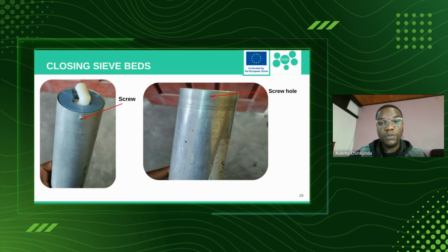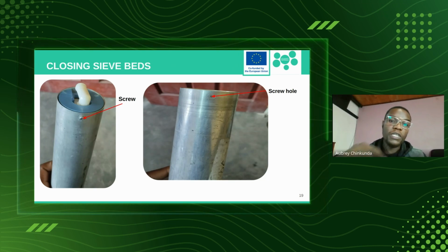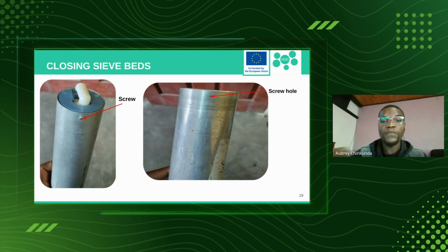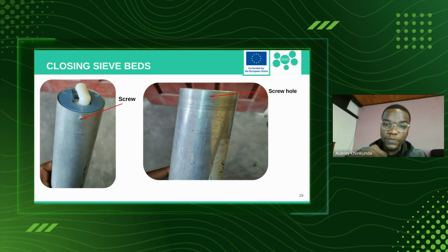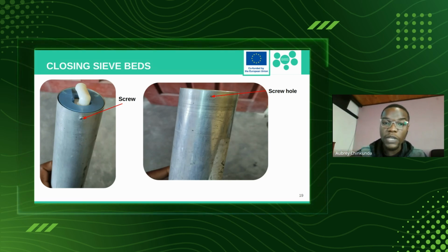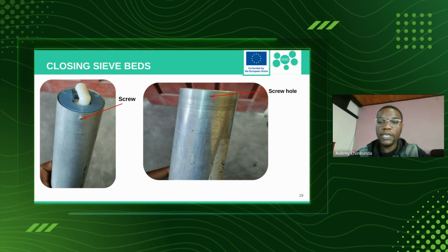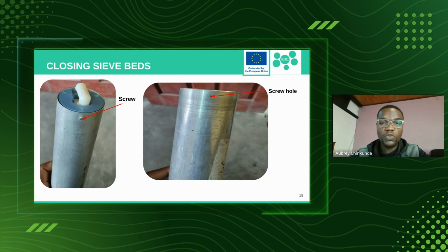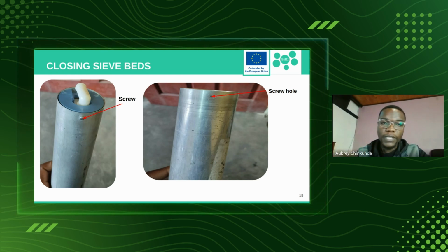So for the non-refillable sievebeds, since we cut them after we have designed the end cap, one way of fastening those end caps is we just drill a hole and we use 3 screws. So in the image, you can only see 1 screw, but there are other screws on the other side, and we tighten the screws to make sure that the plastic end cap is secure and it is safe.